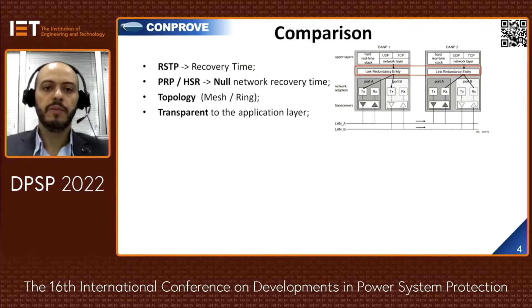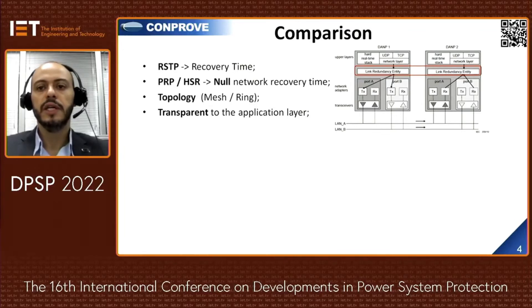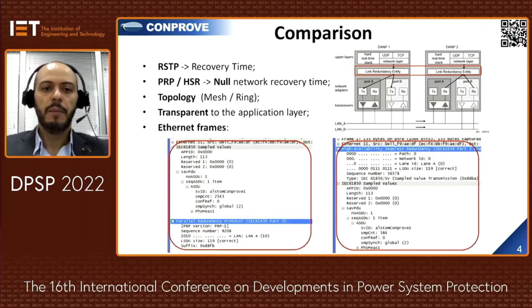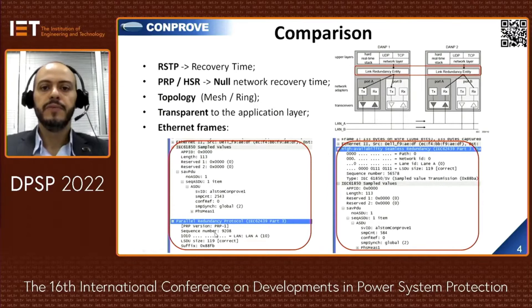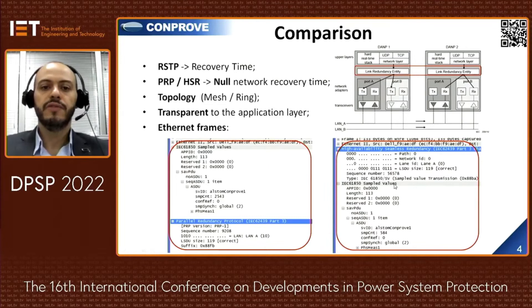An important aspect to consider about both PRP and HSR is that they are transparent to the application layer. Regarding where the link tag is located in the frame structure: in PRP, the tag is located at the end of the frame, as shown in the figure on the left. In HSR, the tag is located in the middle of the frame, as shown in the figure on the right.